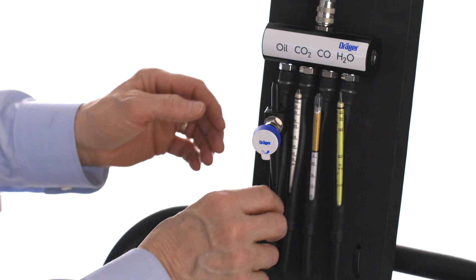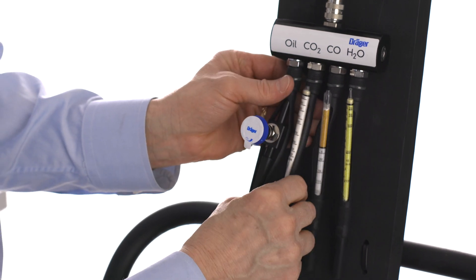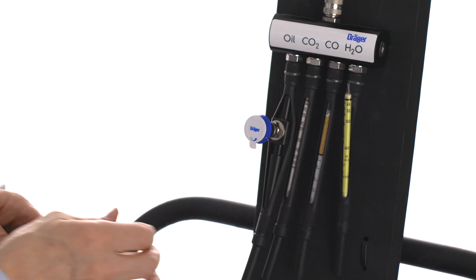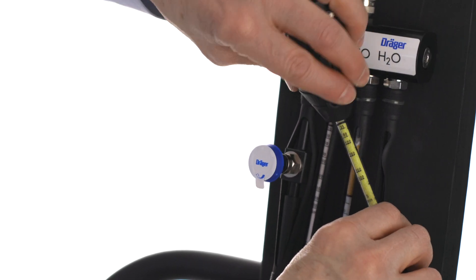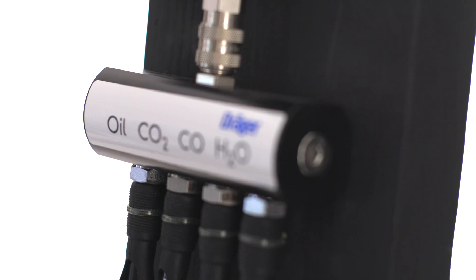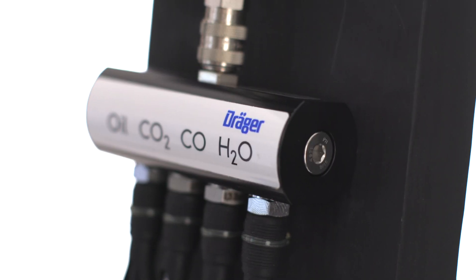Start a 5 minute timer and immediately connect the oil impactor and the tubes, except the water vapor, to the inlet of the holder. Then use the tube opener to remove the tip from the water vapor tube and connect to the inlet of the holder. The oil, carbon dioxide, and carbon monoxide tests are complete in 5 minutes and the water vapor in 10 minutes.